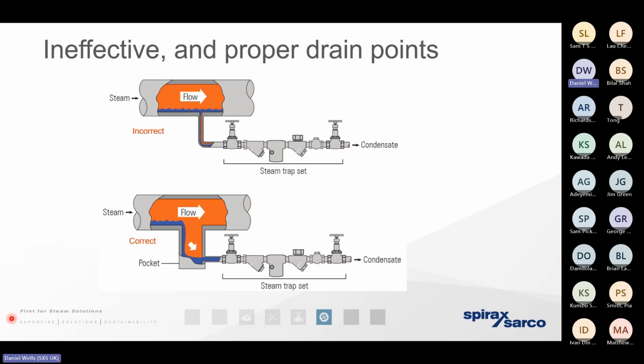We want to ensure that we've got a well-designed, well-engineered steam trapping station. Typically, it's a downward pointing T. That T should be line size, and we should have a dropper leg on the T that's got a vertical drop of probably 2 pipe diameters. That way, it's a very, very generous reservoir. So any condensate that's present in the infrastructure can drain out quickly and easily. We can get that condensate away, but we can ensure that the steam remains at its driest.